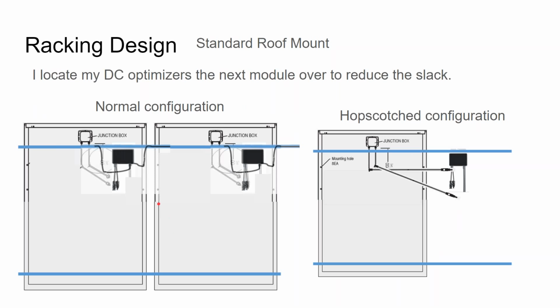I've developed a system where normally the optimizer is right underneath the module, and you bundle the cable up underneath the module as you lay it down, positioning it between the optimizer, the rail, and the module frame so it's not spilling down onto the rooftop.